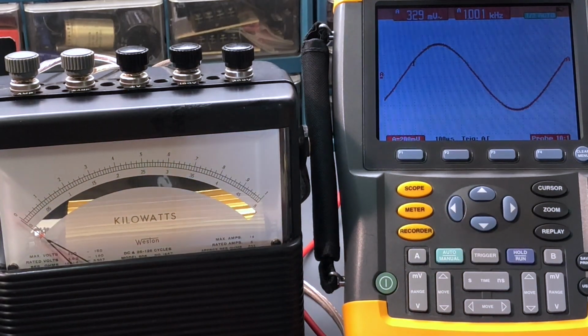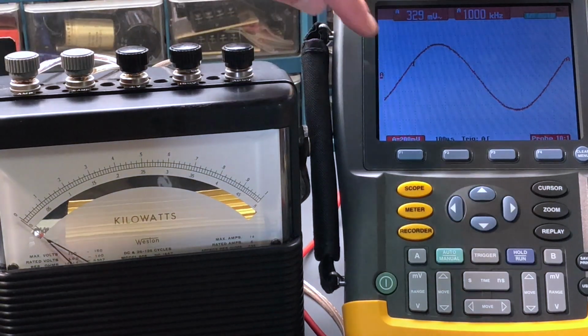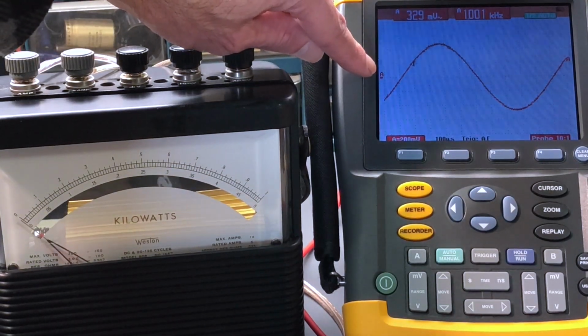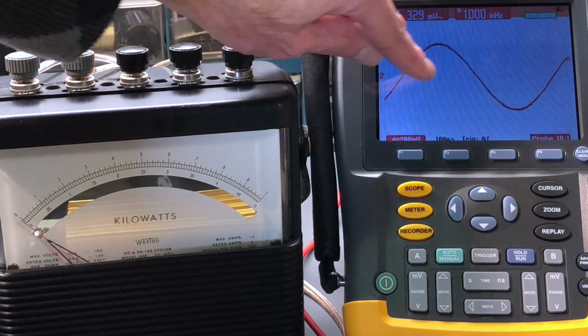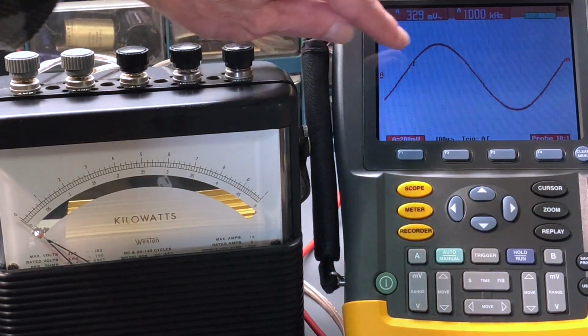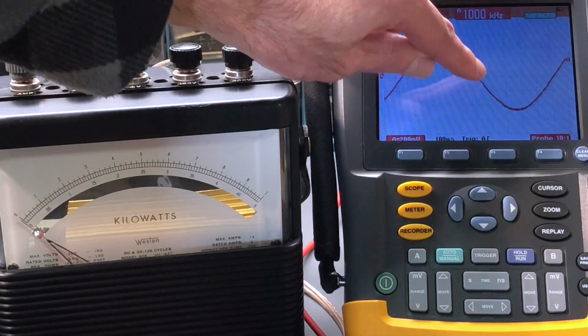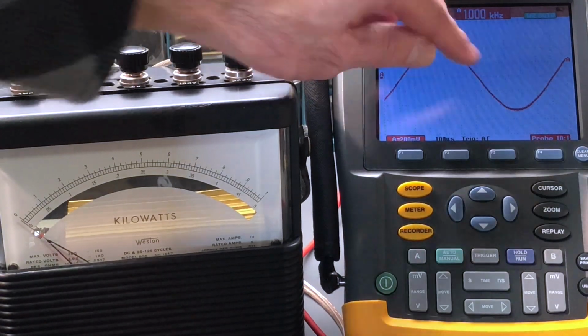So you can see we have a 329 millivolt sine wave right now for the amplitude voltage reading, and the ground reference is where that letter A is right there, through that graticule. And you can see that when it crosses the waveform through the ground reference, there's no step or distortion, and that's very important.